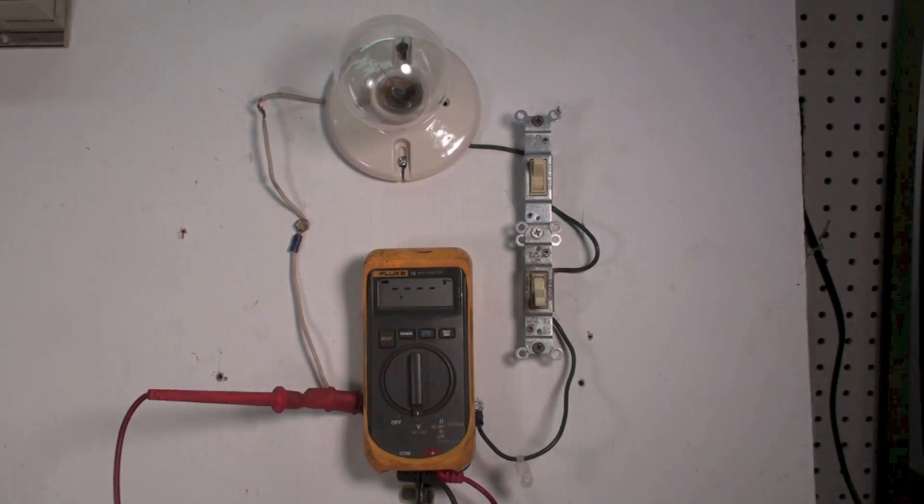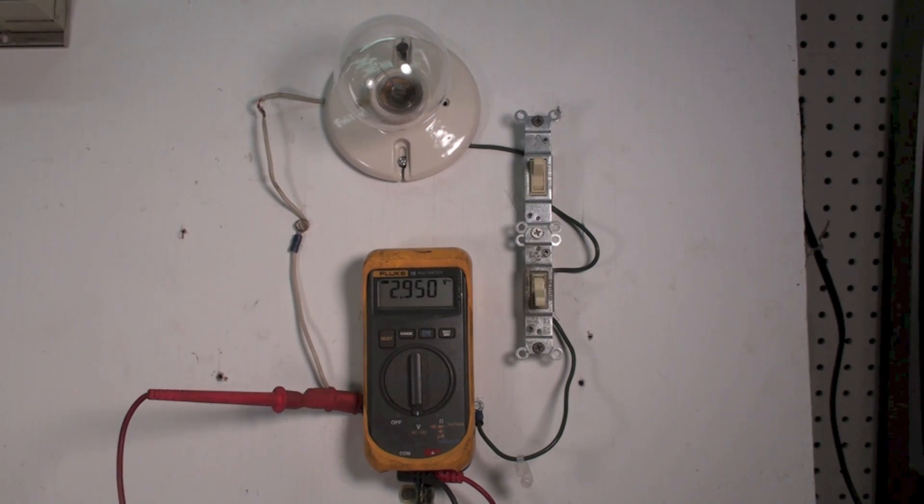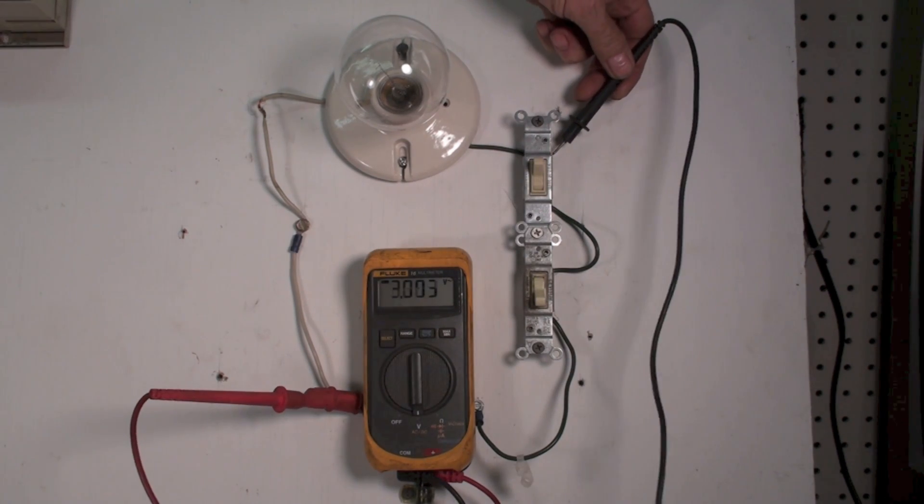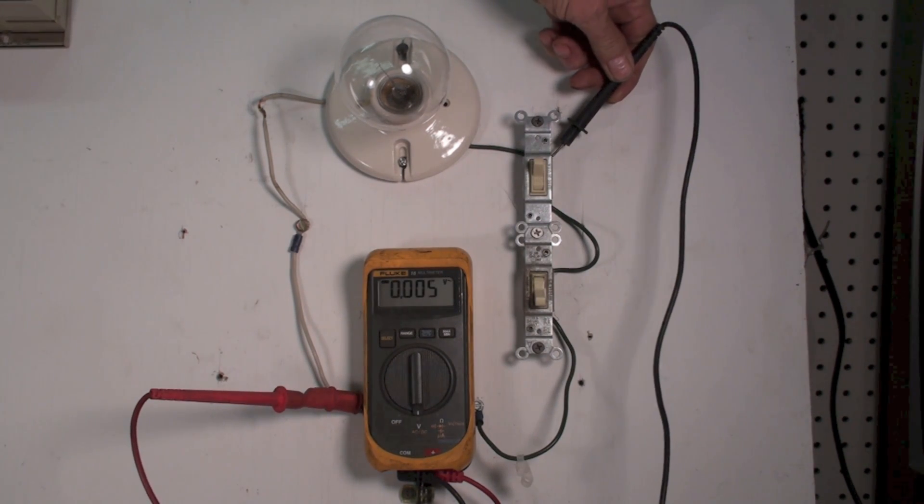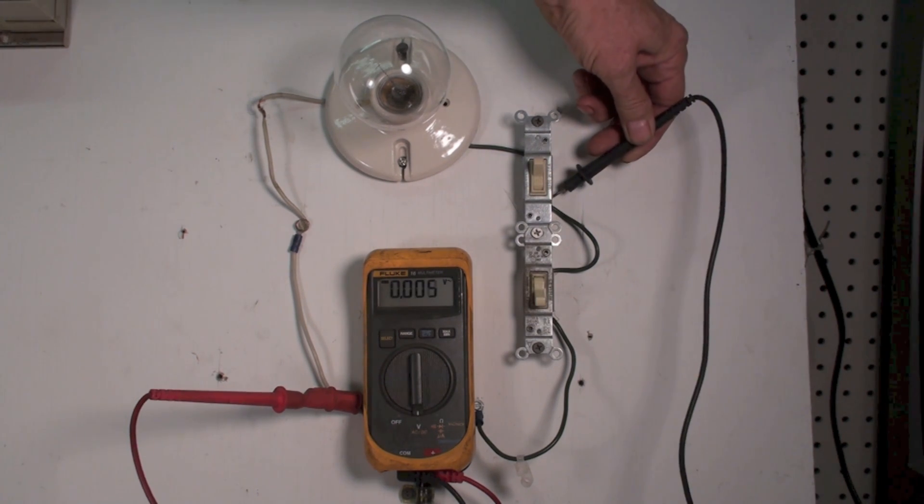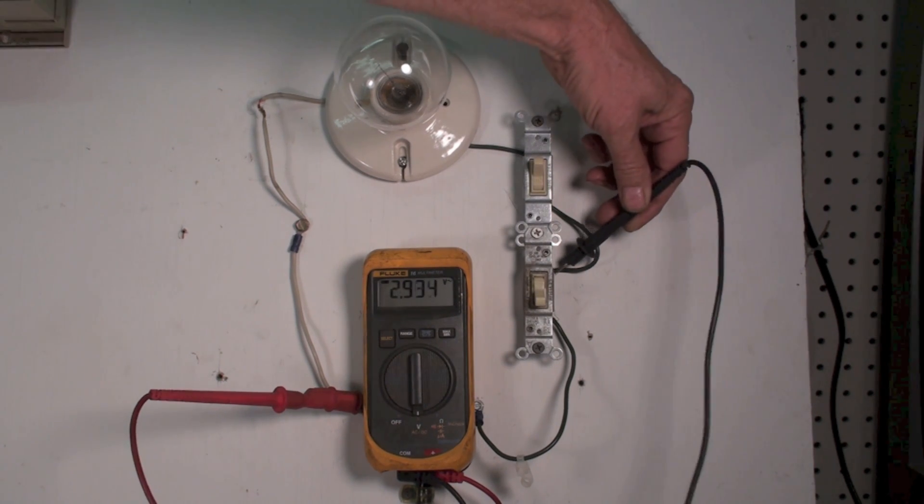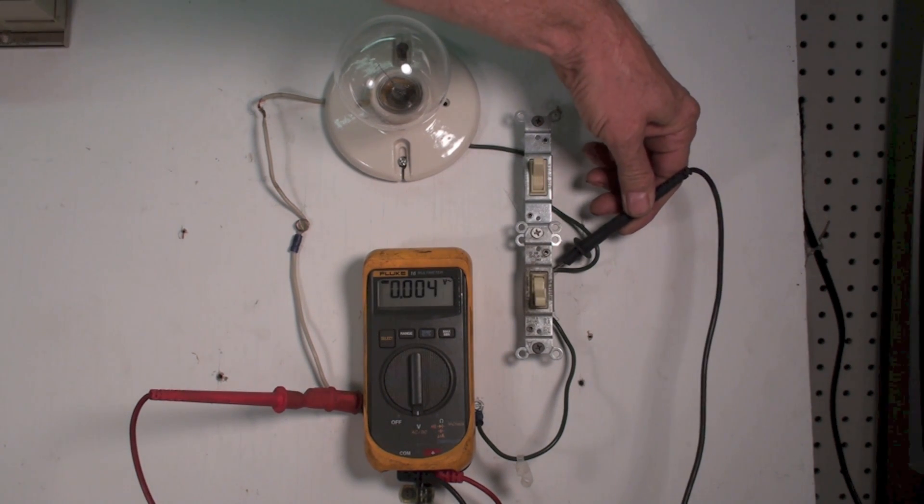And I read voltage. That's telling me voltage is available. Now because this is going up to the load with no switch, then I can go over to here, which is directly to the load, and I still don't see voltage. Now I can go here, I still don't see voltage.